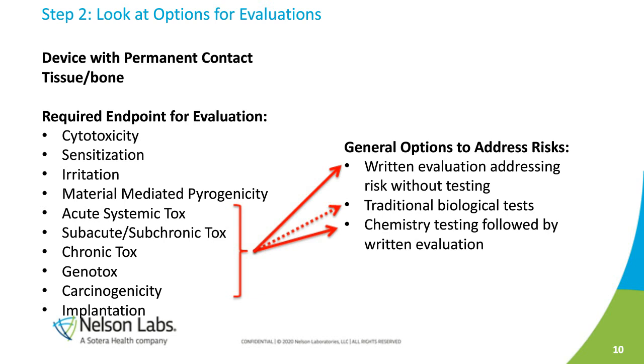So it can be done pen and paper without any testing. More often than not, devices are more complicated than just a single material like anodized titanium. And so we see a lot of folks doing chemistry testing followed by a toxicological risk assessment to address those endpoints.